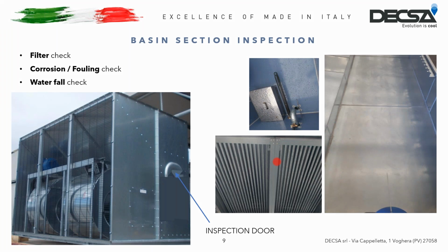That said, with the water inlet system always operating and the motor always off, we can proceed to check the water flow from the exchange coil on the bottom of the basin, from this to this. If the rain from the coil falls evenly from all surfaces, it means there are no clogging problems.